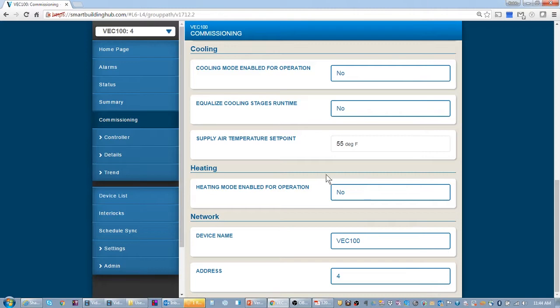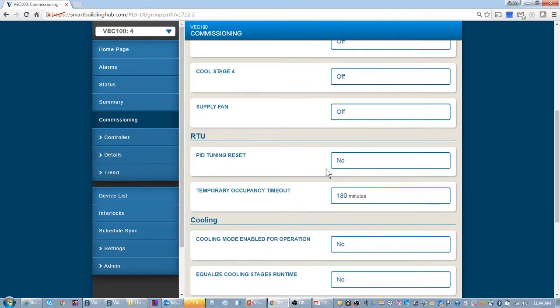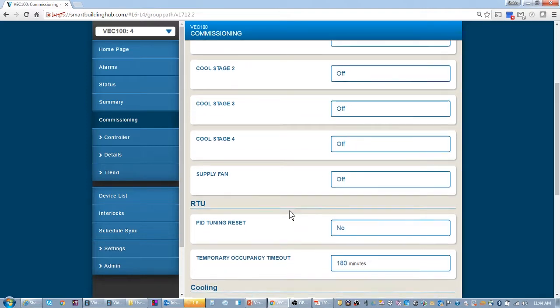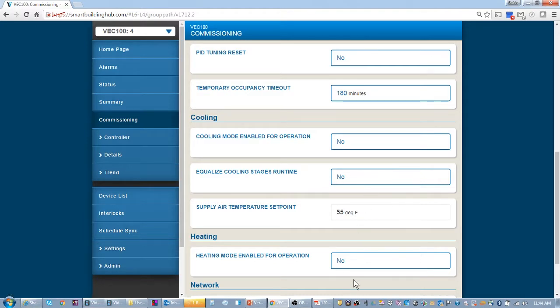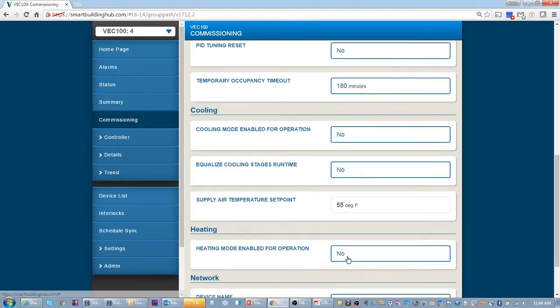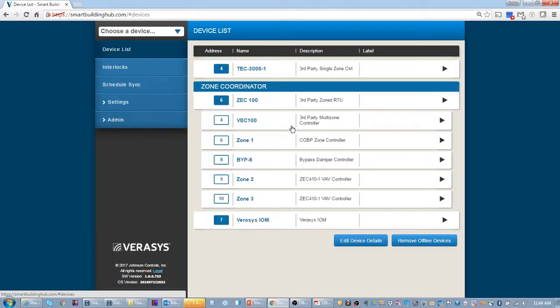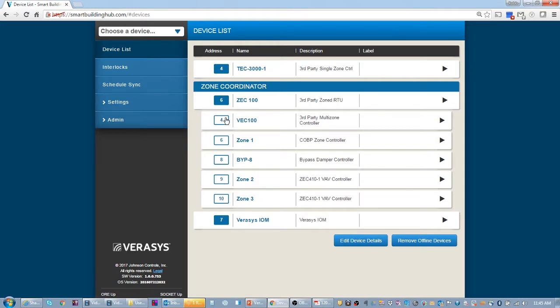I could go through and set anything I want to do for my cooling stages or my heating stages. I like to keep my address set to four. And here's kind of why. I always like my unit to be the first device in the long list of things. So you could have a lot of zones. And if you put it in the middle, you're going to have trouble finding it. But you notice these zones come in and the zones are wired to the zone bus. So they come in order of address.